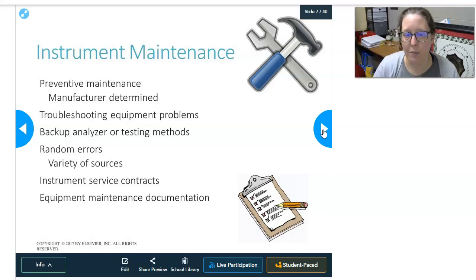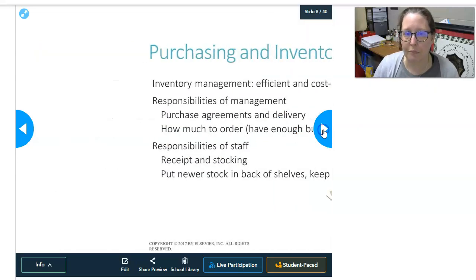And then any equipment maintenance has to be documented. Basically, it's just like everything in the lab. If you don't document it, you basically didn't do it. There are usually ways to log it. Now you can even log it on the instrument computer itself. Often there are clipboards or things around where you can initial what you have done. You also want to keep records of any troubleshooting, parts replaced, and all of that. You should be able to track everything that's been done to that analyzer.